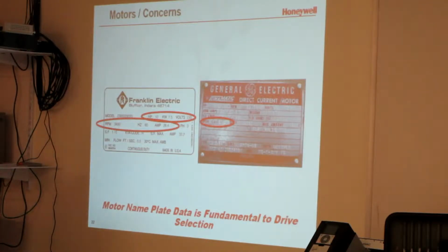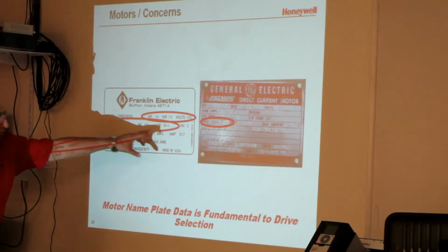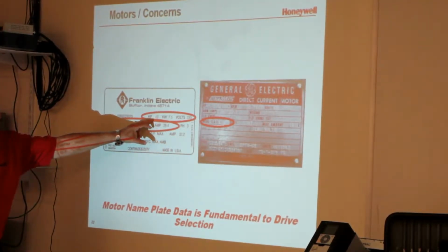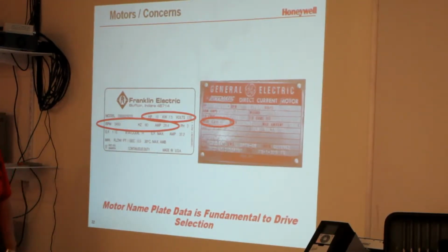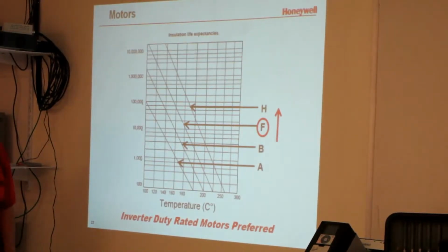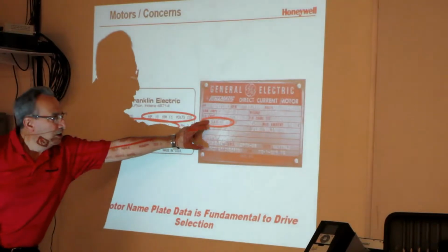Now, when you're setting up a drive, a couple things you look for. First of all, you need to order the right horsepower and the right voltage. So you look at the motor, and for those of you who are experienced and have worked with motors before, you know that when you go to look at the motor plate, you bring a rag and some squirt cleaner, because chances are that motor plate is dirty. Hopefully no one painted over it. I've seen that. We'll paint everything blue today. Okay, well, it's going to be hard to read the plate, but if you can get the plate clean enough and you can read it, what you want to do is check the RPMs, the amp draw, the horsepower, volts, and also the insulation class of the windings.